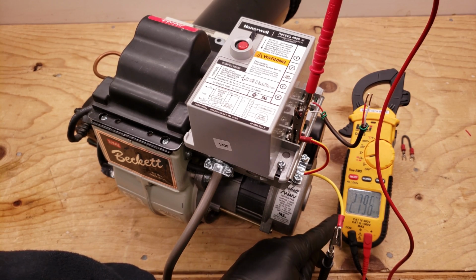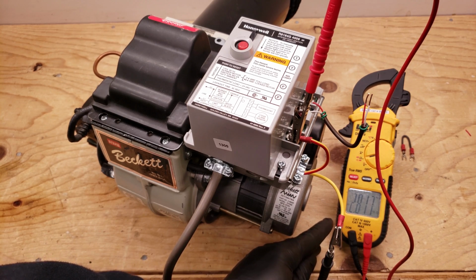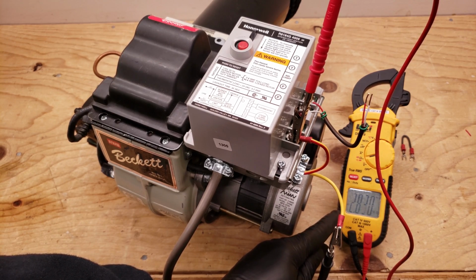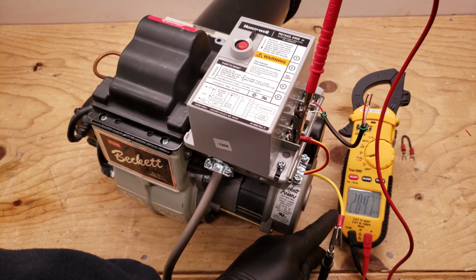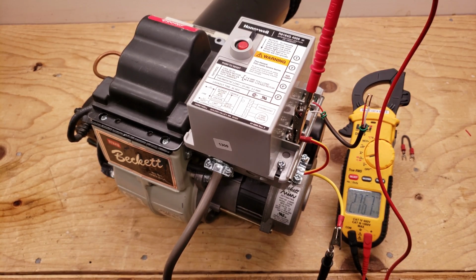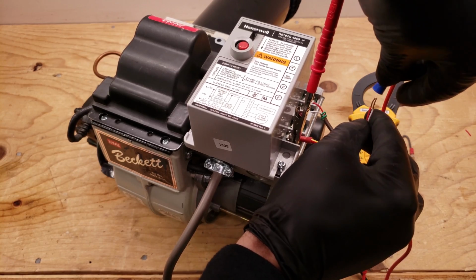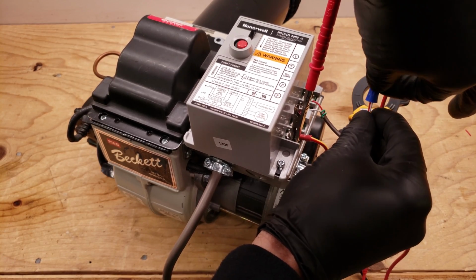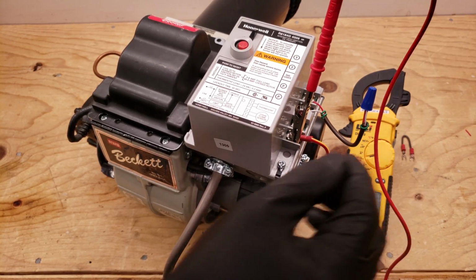And if we read OL, then maybe the multimeter is off, or maybe the actual CAD cell itself is opened up on the inside. You also don't want to have something like 0.0 ohms. That's definitely bad. It should definitely change with the amount of light that it sees. I'm going to be doing a test now, and I'm getting ready to turn the power on, so I want to make sure my TT terminals are connected.